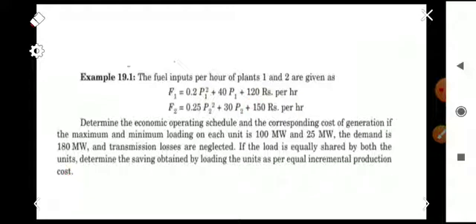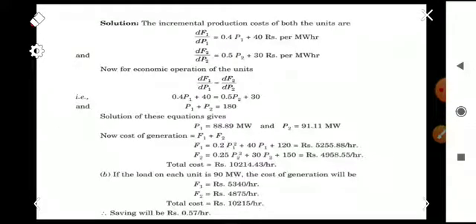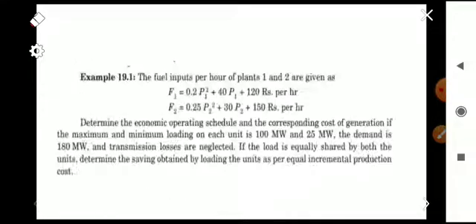If the load is equally shared by both units, determine the saving obtained by loading the units as per equal incremental production cost. For optimum load dispatch, we must know that dF1/dP1 should be equal to dF2/dP2.